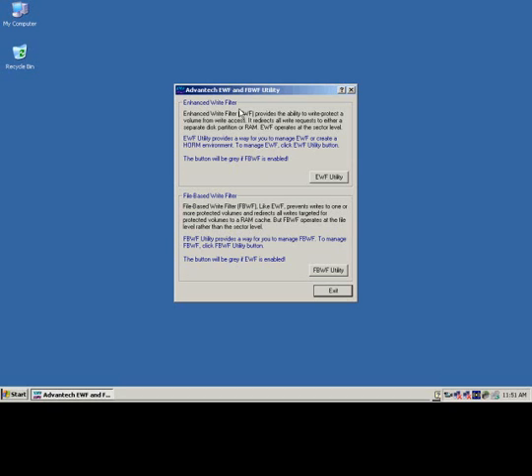The Enhanced Write Filter is what we're going to do first. What the Enhanced Write Filter does is it will protect the entire hard drive. If you're not doing data logging, that's a great way to do it because you can protect the entire drive at one time. If you are doing data logging, I would recommend using the Enhanced Write Filter instead of the File-Based Write Filter, strictly for the fact that you can save your data files to a USB drive. That USB drive will not be protected by the Enhanced Write Filter, and you can do all your data logging to the USB drive.